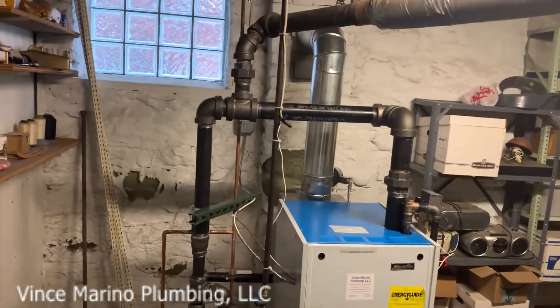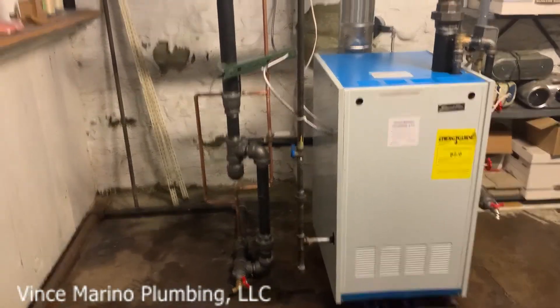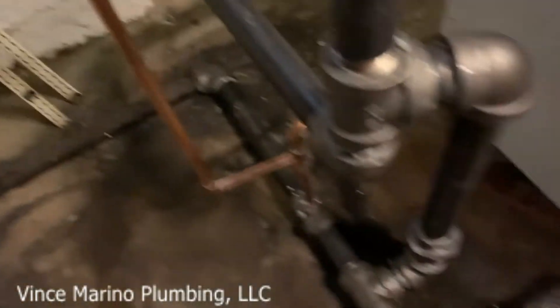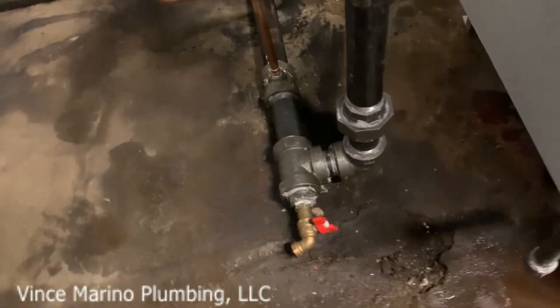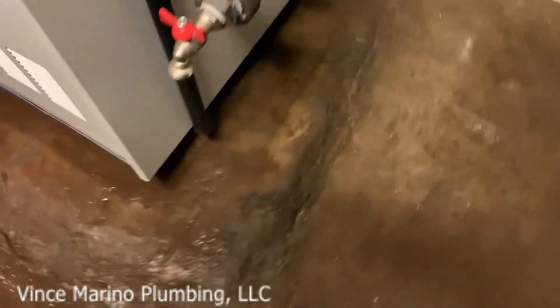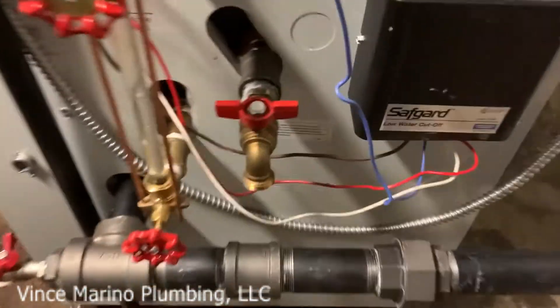This is September 24th, 2020. And you always want to put a drain at the bottom of your Hartford Loop — one going into the boiler and then your skimmer. This is the skimmer valve here. Cross view of the header: two and a half inch to two inch.